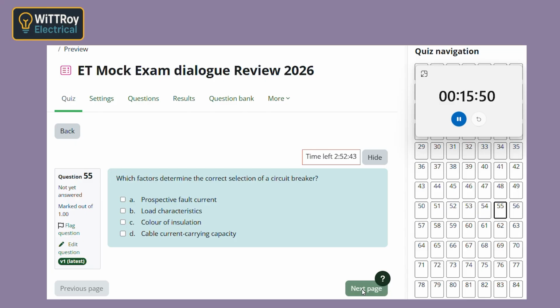Exactly. Cable current carrying capacity matters because the breaker must protect the cable. If the breaker rating is too high for the cable, it may overheat before the breaker trips. And load characteristics? Yes, some loads like motors have high starting current, so you choose a breaker characteristic that allows normal starting but still gives protection. So color of insulation is obviously not relevant. Correct.